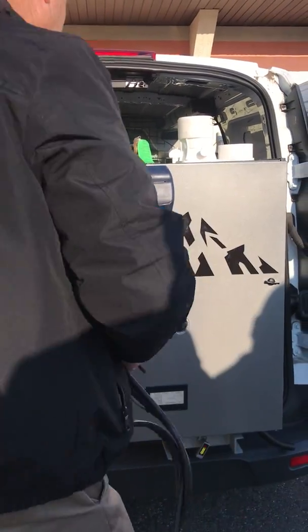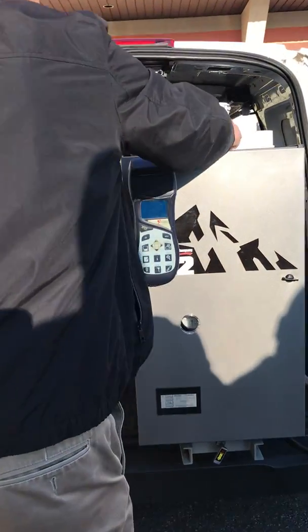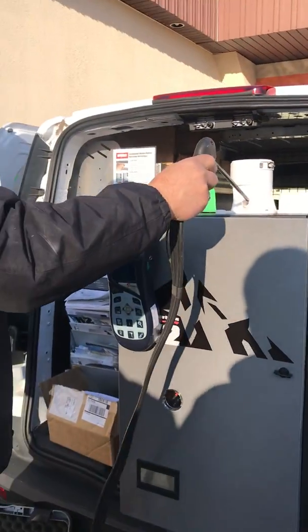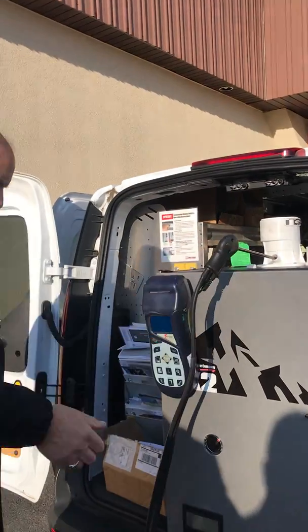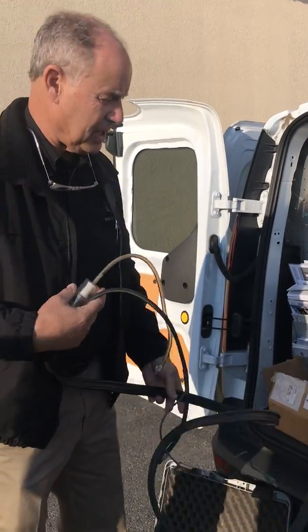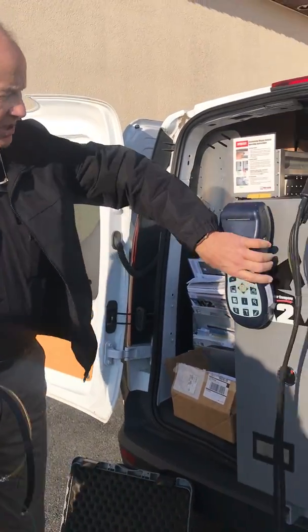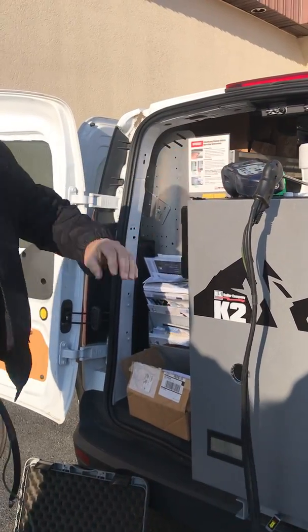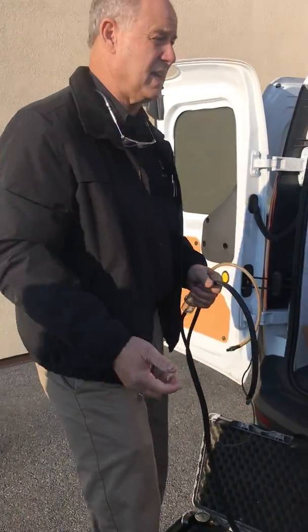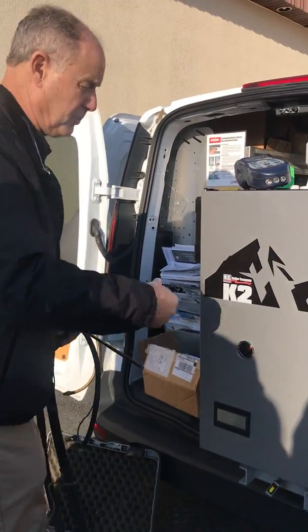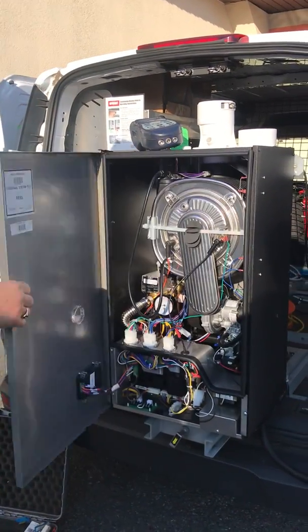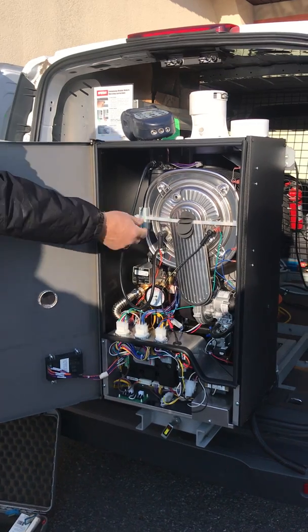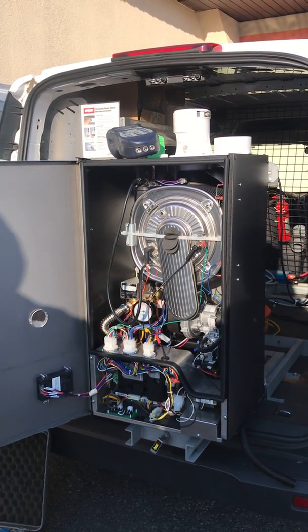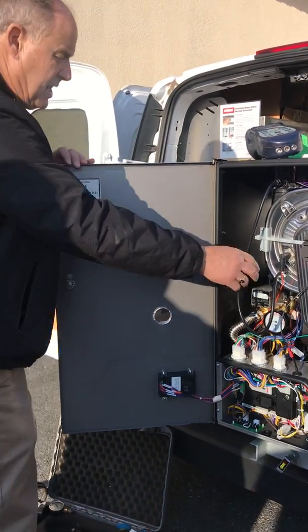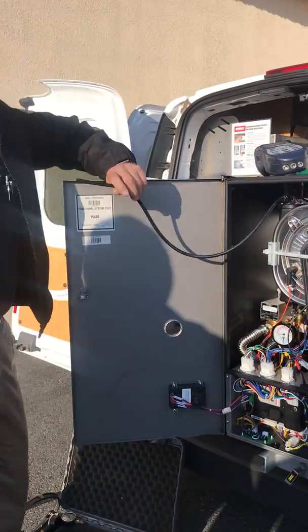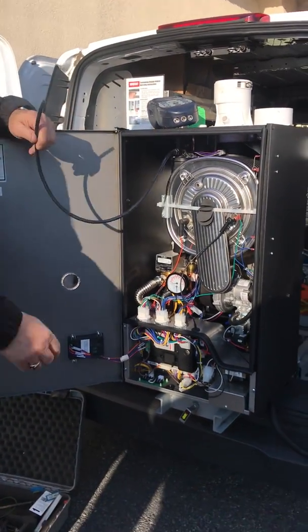When you guys are setting up equipment, number one, especially if you're converting from natural to propane, you need a combustion analyzer so we can actually check our products of combustion. And when we're doing it, I was asking what you guys do when you convert it from natural to propane. And to convert this boiler from natural to propane, this is just a shipping strap. Right. And one of the problems, just by the way, this little hose here, this hose is for bleeding the air out of the heat exchanger.